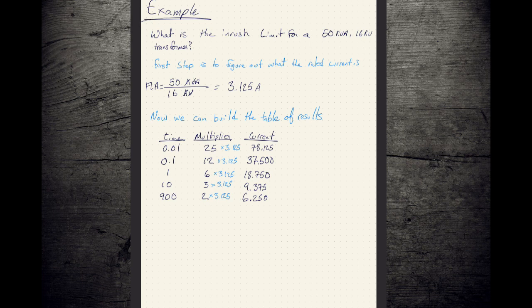Well, our first step is we have to figure out what our full load amps is. So what's our full load current? We can do this by taking our 50 kVA, put it over 16 kV. K cancels with K, V cancels with V, we're left with A. We know we did it right, yay for unit analysis, and we get 3 1/8 amps.